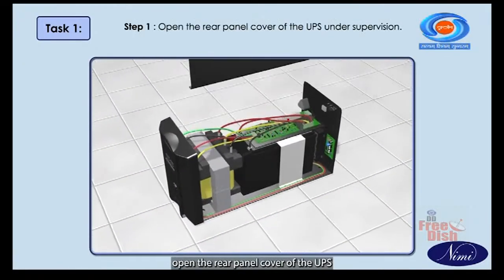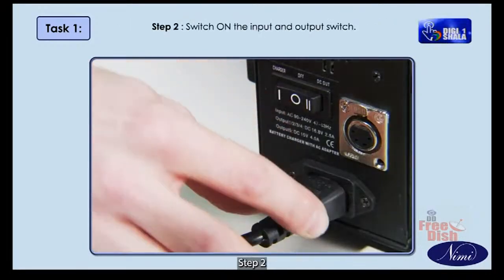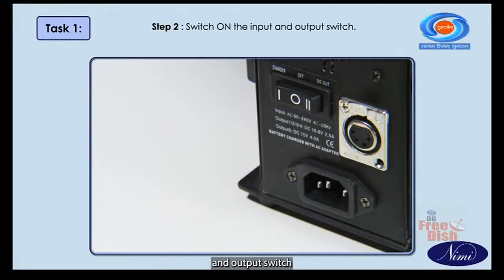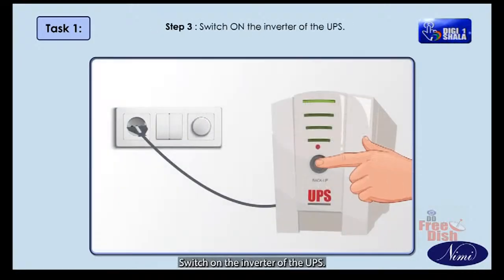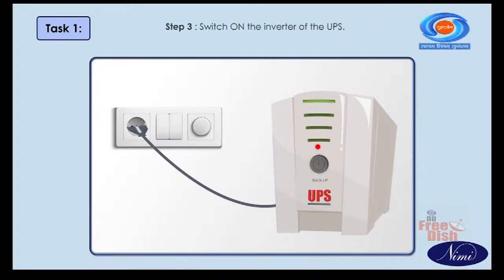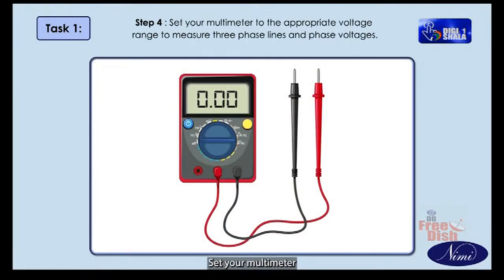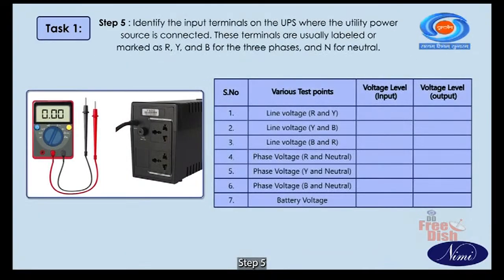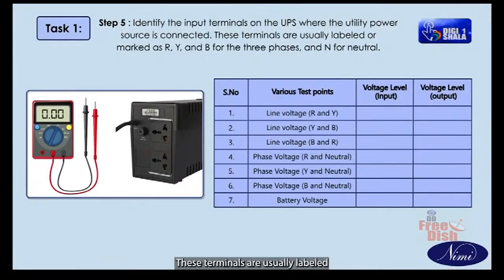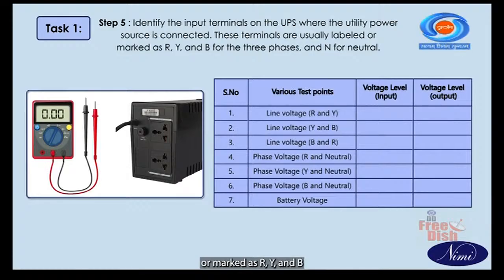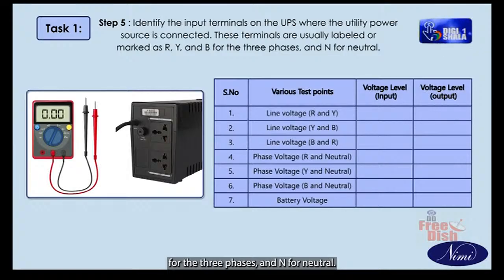Step 1. Open the rear panel cover of the UPS under supervision. Step 2. Switch on the input and output switch. Step 3. Switch on the inverter of the UPS. Step 4. Set your multimeter to the appropriate voltage range to measure three-phase lines and phase voltages. Step 5. Identify the input terminals on the UPS where the utility power source is connected. These terminals are usually labeled or marked as R, Y, and B for the three phases and N for neutral.